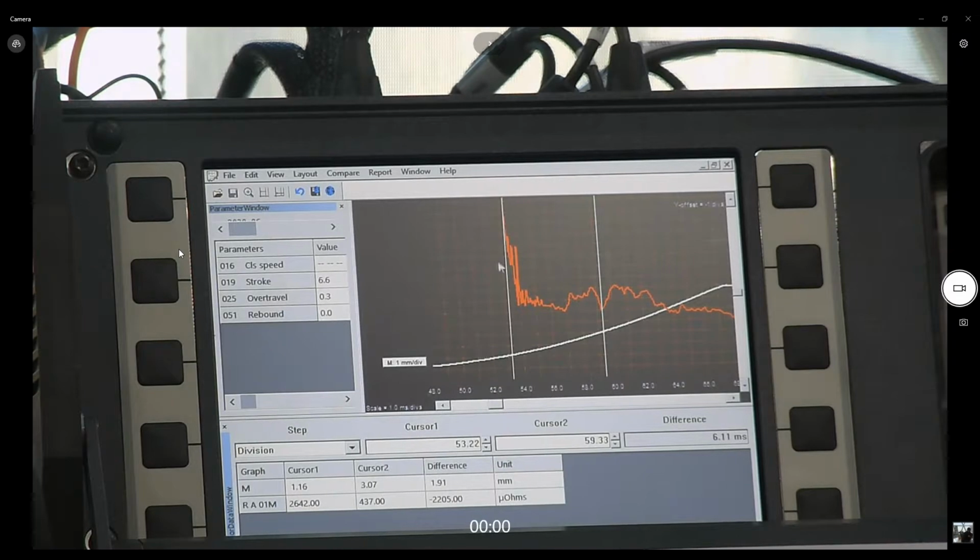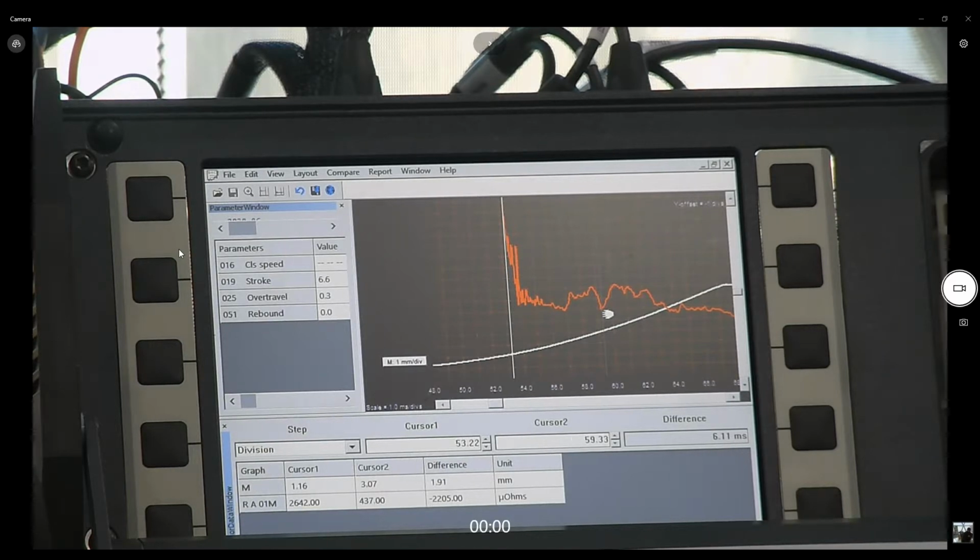Here, and then having 2 millimeter difference, for example, should be very similar to the opening, but as I mentioned earlier, I'm taking my motion measurement from my circuit breaker simulator. That's why the values are not consistent with each other, but in a real environment, it will be so. This is just an example to show you how the DRM and the SRM work.